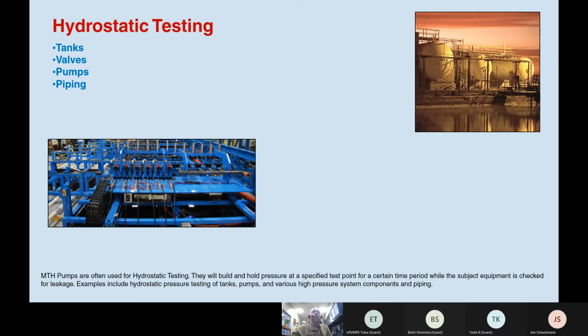And then hydrostatic testing. Any facility that makes tanks, valves, pumps, or piping has to have some kind of regulation as to how much pressure that tank, pump, or valve can handle, and or some kind of leak test. And so we use our pumps because they're made for the high pressure without the high flow. You can simply plug all the holes in a tank or a pipe or whatever unit you have, and hook our pump up to it with one inlet and one discharge on a valve with a pressure gauge, and simply let it run at whatever pressure you need to test it, and check for leaks and move on. It's a quick and easy way to do hydrostatic testing without having to mess with air pressure and everything else.